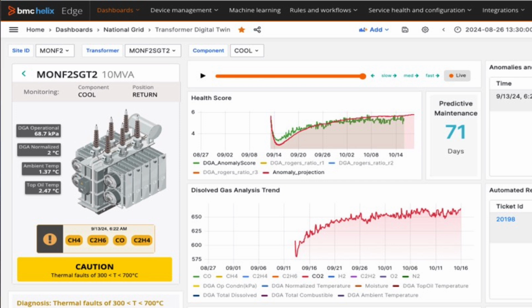And their biggest problem is they either fail without knowledge, so you can consider that unplanned downtime if that's what you want to call it, or they don't last as long as they should. So if it's rated for 100,000 operating hours, maybe they only get 90,000, right? Also an expensive proposition. In other cases, they are told to replace those at 100,000 hours, and they do religiously, but did they really need to replace it? So that's the problem set they're starting with, right?